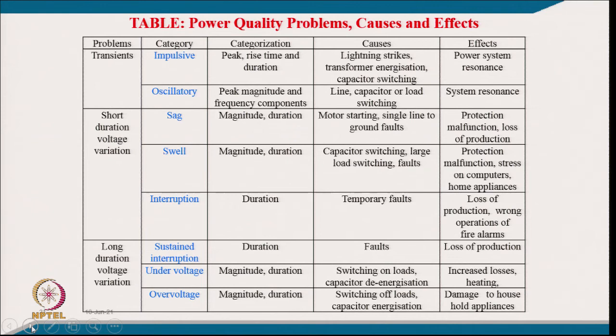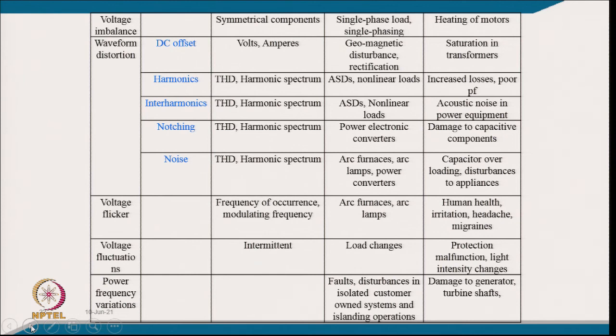Long-duration voltage variations include sustained interruption defined by duration, caused by faults resulting in loss of production. Under-voltage is quantified by magnitude and duration, caused by switching on loads and capacitor de-energization, increasing losses and heating. Over-voltage is caused by switching off loads and capacitor energization and damages household appliances.